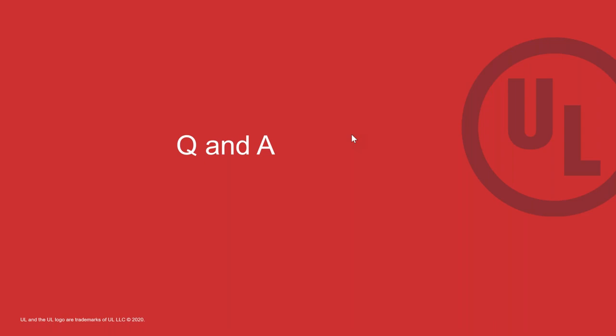Very good question. Basically, short circuit rating depends upon the end buyer, or maybe consultants, or maybe utilities. Depending upon the utilities' requirement, for example, normally main distribution boards, maybe 50 kA, normally everybody uses. SMDB, 36 kA to 25 kA. FDB normally goes with 10 to 17 kA.